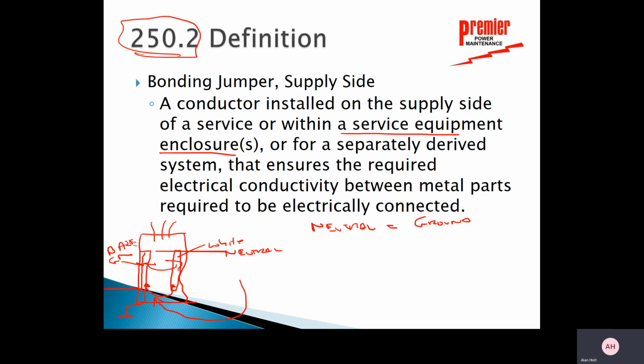But what I found out after he got to the point where he could talk to me, was that this was a bonding jumper. So that bonding jumper was at the service equipment. There it is. At the enclosure for a separately derived system, separately derived because out on the pole there was a transformer. And no, there's no electrical connection from one side of the transformer to the other. So this secondary, the 120/240 volt single phase house service, was a separately derived system. Completely different electrical system than what the primary side of that transformer was. So that was a little hard for me to grasp at the time, but I understand it now.